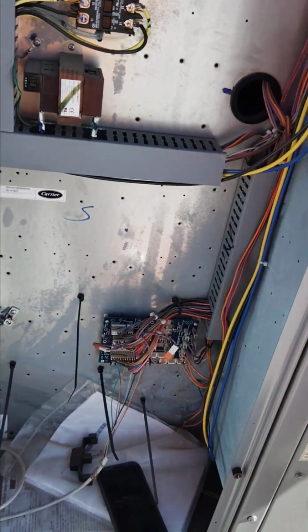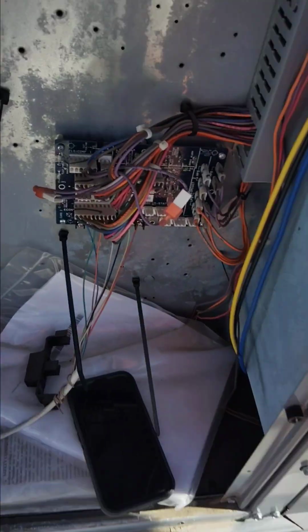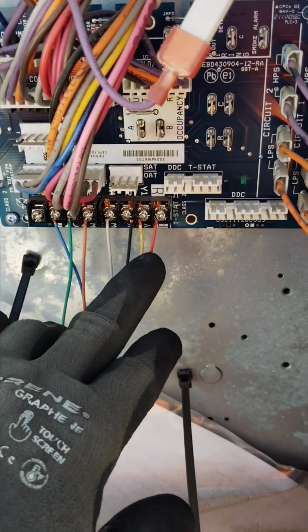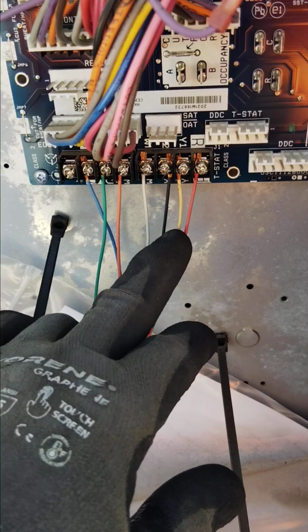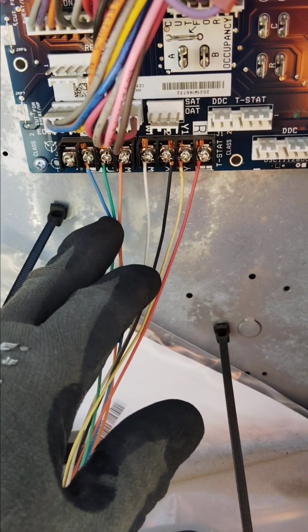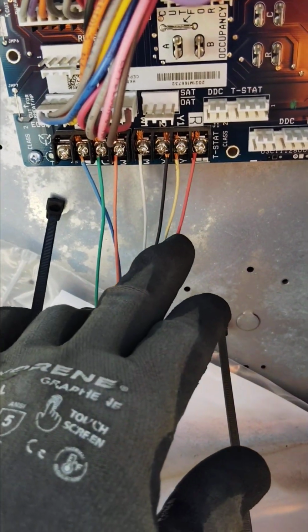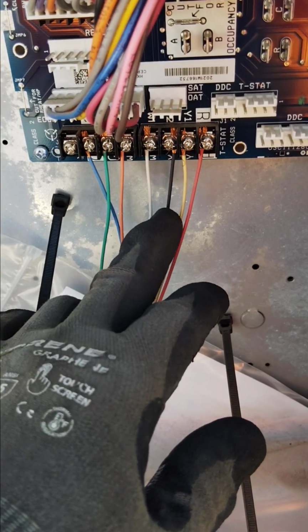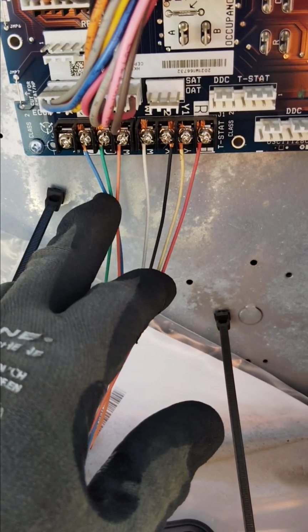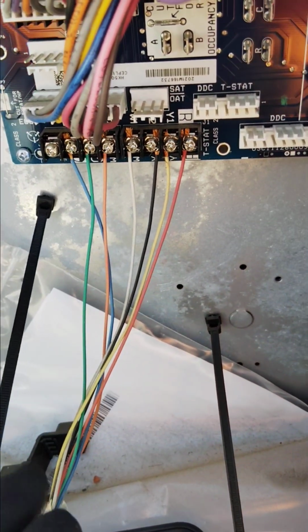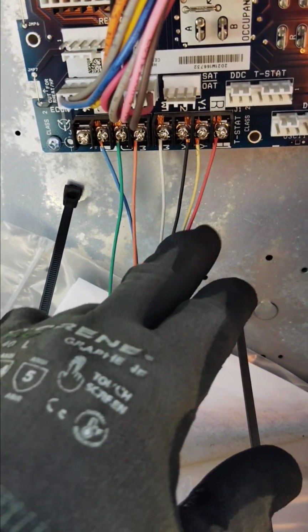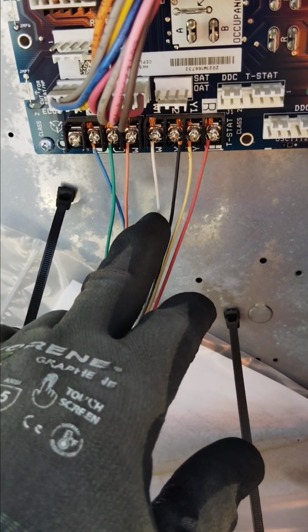So what we do, we just put this system into test. We jumper the low voltage. We have red, yellow, and green for the fan. We can jumper stage 1, stage 2 with the fan to at least get it into cooling. For heating, you're gonna jumper red and the W, or the white wire, and that will turn on the heat.